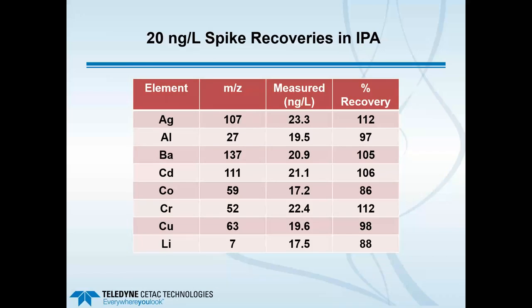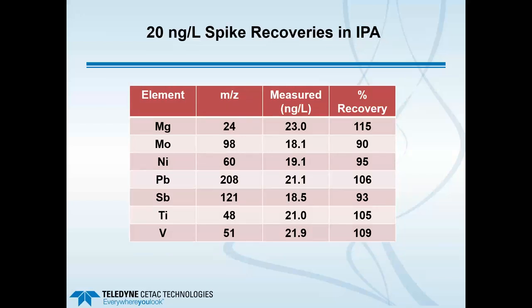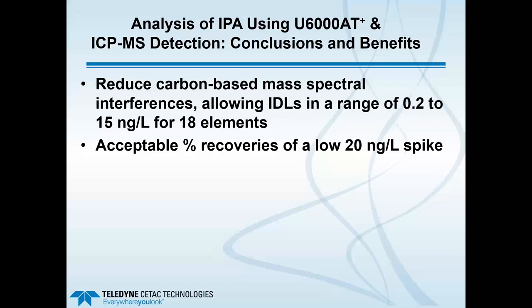For spike recoveries at the lowest calibration standard of 20 parts per trillion (20 nanograms per liter), all recoveries are good, running in a range of approximately 90 to 120 percent. All of this was done using reagent-grade isopropyl alcohol and non-cleanroom conditions. Using the membrane desolvation capability, we reduce carbon-based mass spectral interferences, allowing IDLs in the range of 0.2 to 15 nanograms per liter (0.2 to 15 parts per trillion) for 18 elements.